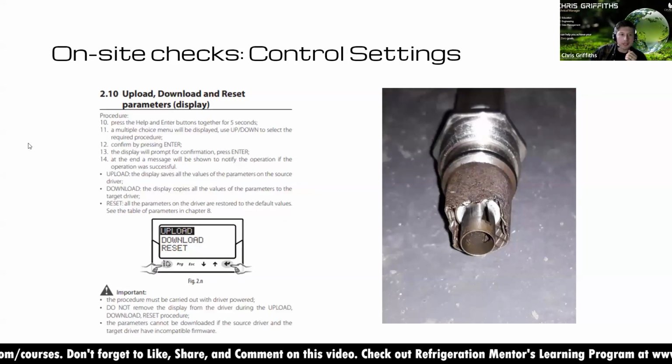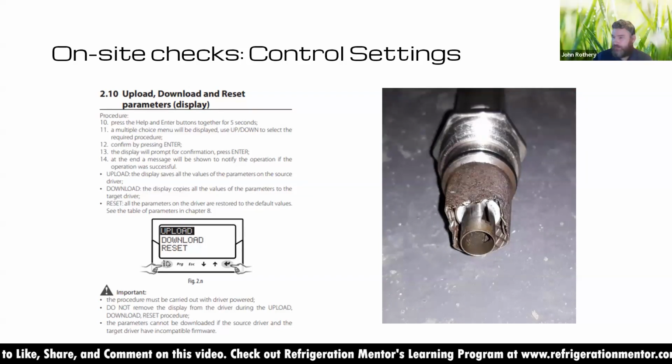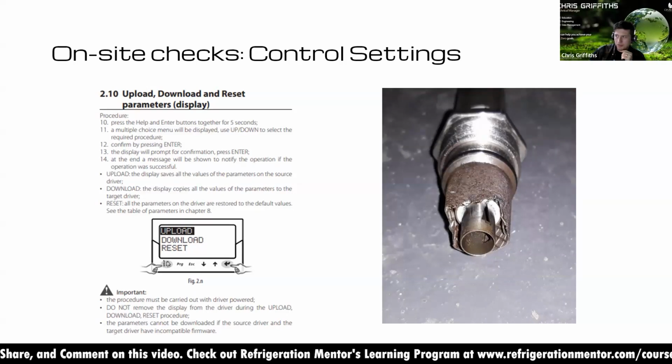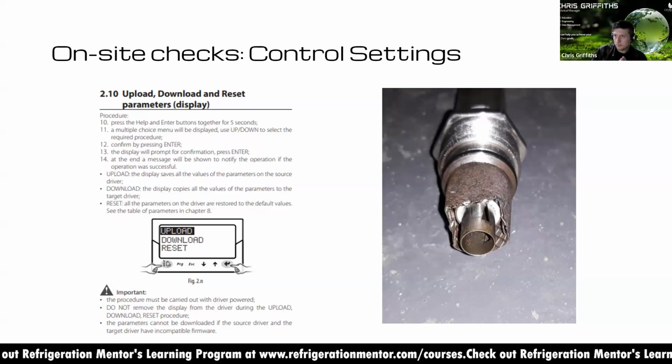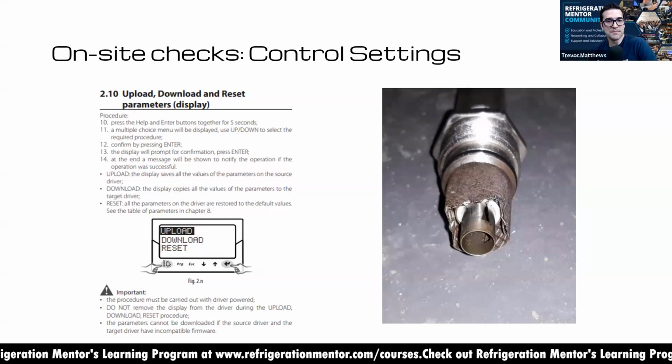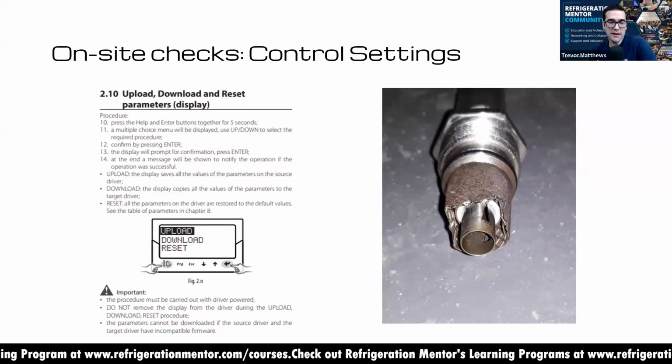So the right-hand picture here is from a flash gas bypass valve, wasn't it, John? Again, very blocked up. Was it the PRV or the high pressure valve? Sorry, I think that was a high pressure valve, that one. So stainless steel, this one. Wow. Yeah, that can cause a massive amount of issues.